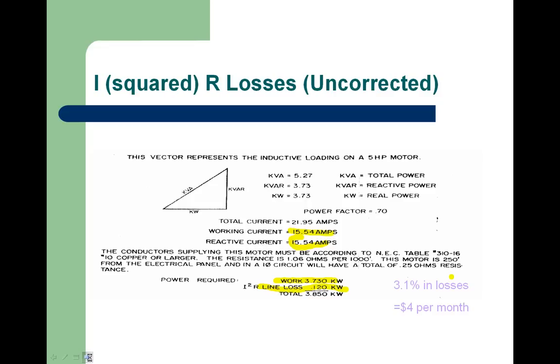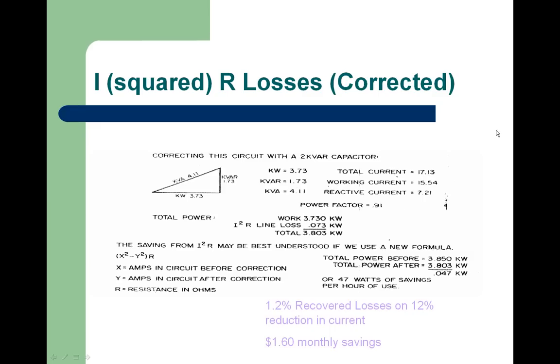On the next slide here, what we've done is they've added some kVAR. So our power factor has now gone up to 91%. You'll notice that our kilowatts are still at 3.73, and our kVA has been dropped down to 4.1. So we now have a similar case. We have our work being done here, which is 3.7, and that would be regardless of where. But we have now reduced our losses from 0.14, which we had in the previous slide, to 0.073. That's because we've reduced our current from 21 in the previous to 17.